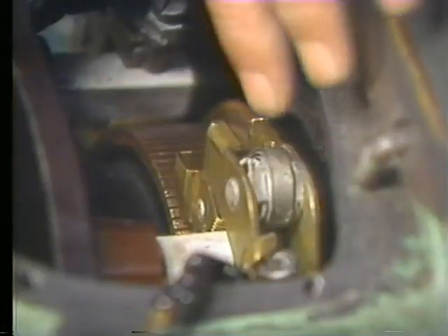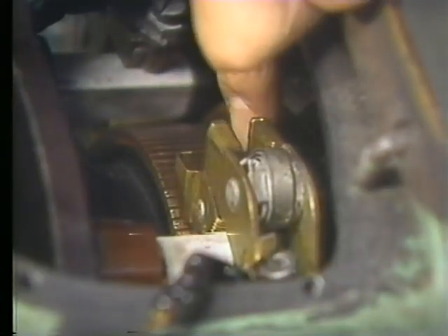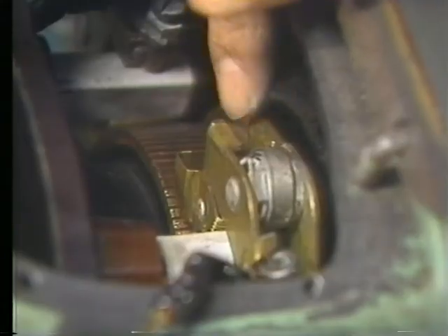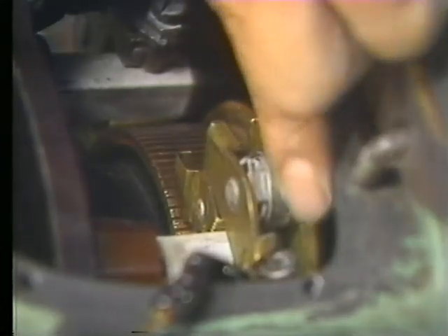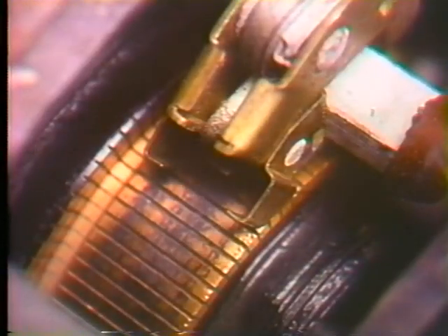Then the inside of the holder to see if there are burrs or bends. The bottom is smooth, no burn spots. Then check the commutator. It looks good. According to what we've seen, there's no reason why the brush, the holder, or the commutator shouldn't be okay. Let's replace the brush in the holder and reset the tension device.